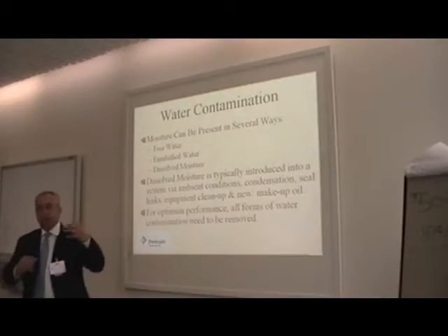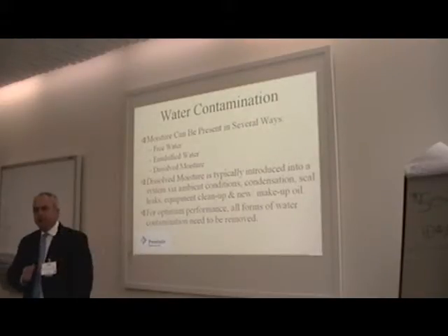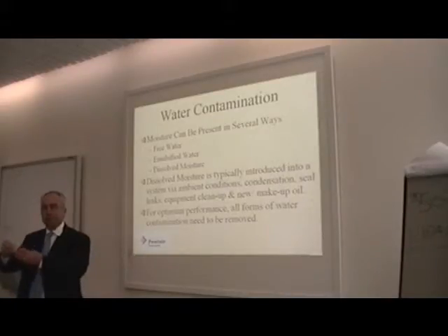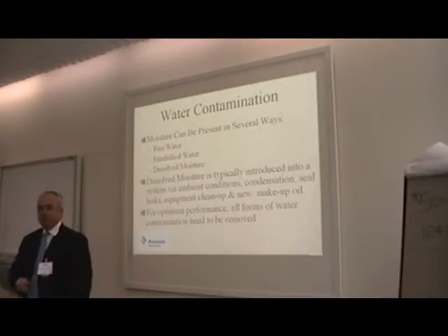We brought in one of our systems, and they looked at it, and they're like, oh, this moisture sensor of yours isn't working, because we have a moisture sensor on board. And it said, basically, saturated. The guy's like, yeah, we've had one of those sensors here, they never work. It's always saturated. We started looking at their oil analysis, and sure enough, the technique they were using started at 1,000 parts per million. The oil saturates at about 160.